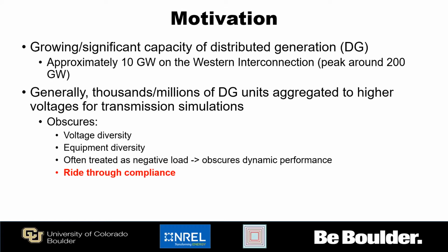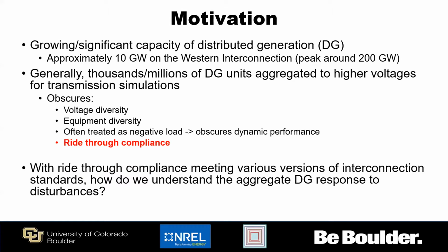Some of the issues with this is that it obscures voltage diversity, and so the voltage isn't the same at every inverter on the system, even though that's how we're modeling it. Equipment diversity, they're not all the same inverter, for example. And we often treat these just as a negative load, which also obscures their impact on dynamic performance. A further issue is that we obscure the ride-through compliance. So that's going to be the focus of the presentation here today.